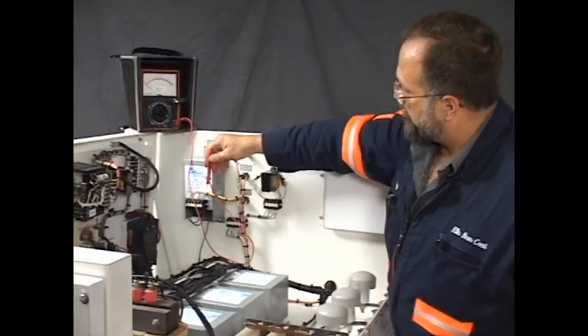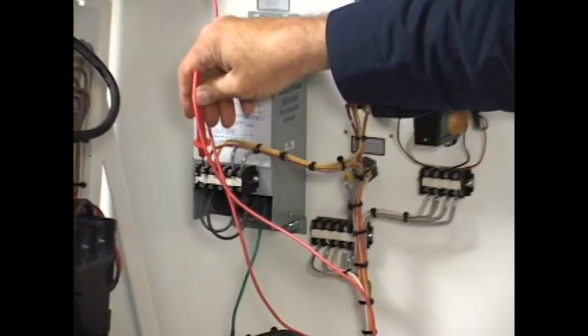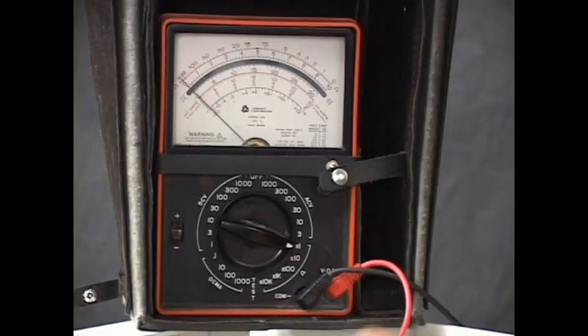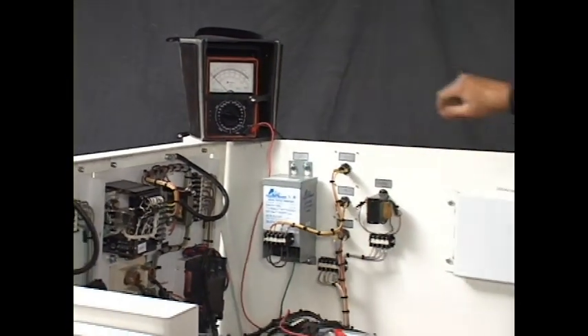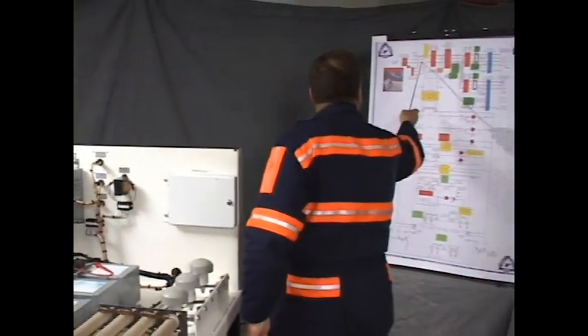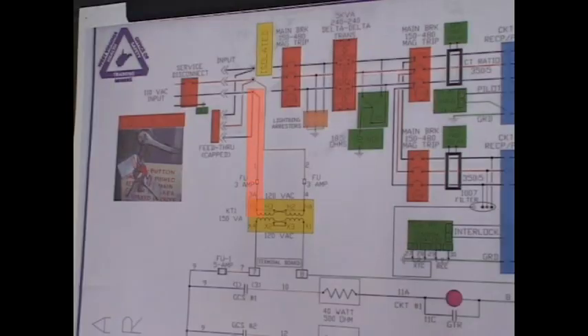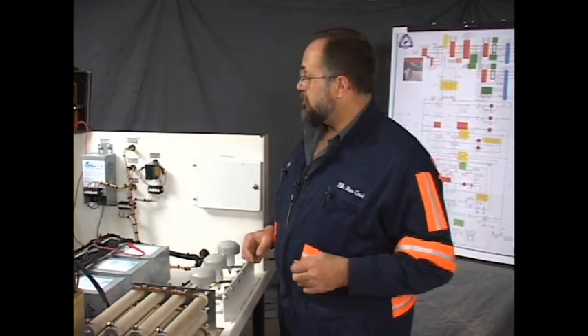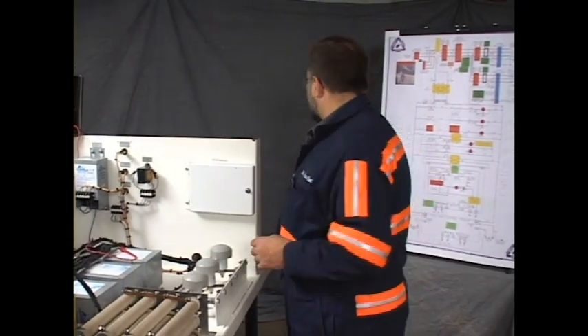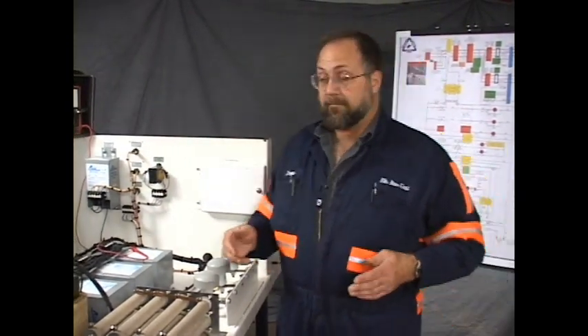I'm reading through the fuse. And the other end of wire 3 is on KT1, and it indicates an open circuit. The needle didn't move at all. No movement. The circuit is open. Note that I've followed this line from point to point, just as if you're taking a map and go from destination to destination. Although there are a multitude of wires on the print and a multitude of wires here, all of the wires aren't bad. Each wire you can check with a simple continuity check from one end of the wire to the other with the instrument.